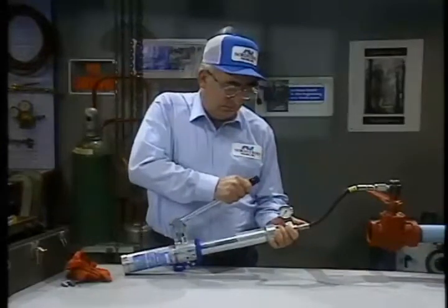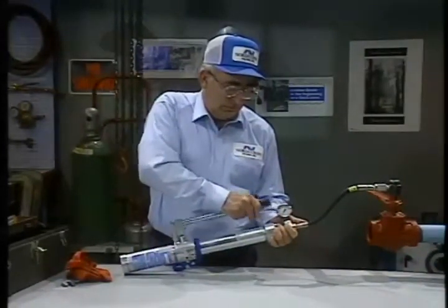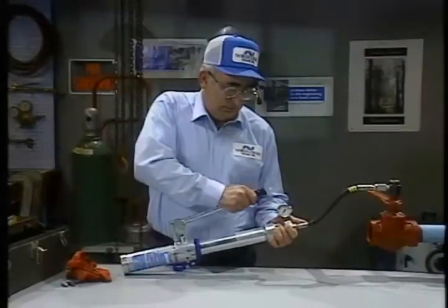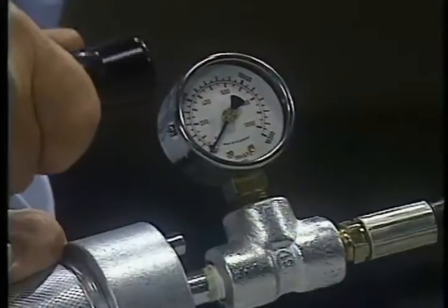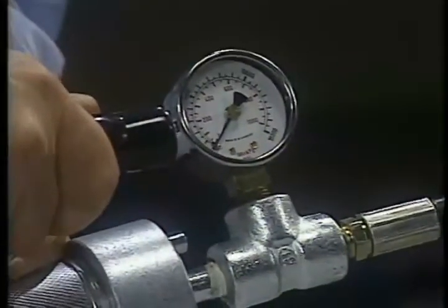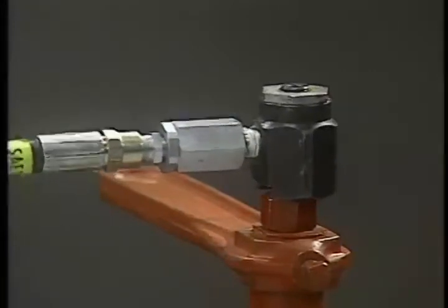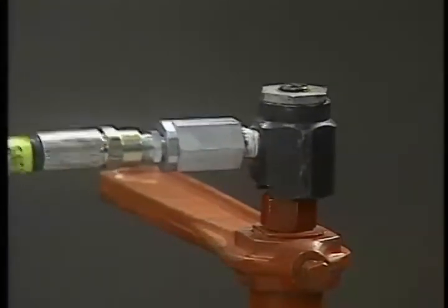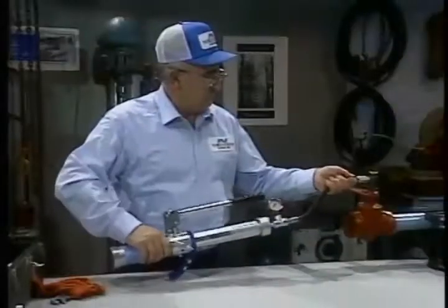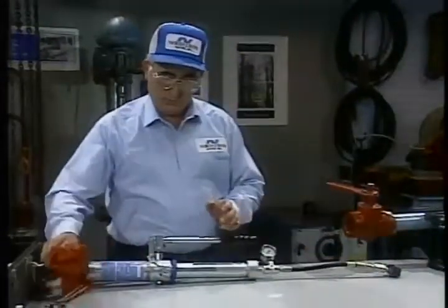You can usually tell when all the sealant has been pumped from the handgun because it will become increasingly difficult to operate the handle. The gauge will not indicate any rise in sealant pressure and may even fall back toward zero. Also, the giant button head coupler normally will become loose on the valve sealant fitting. When these conditions appear, discontinue using the handgun and add sealant.